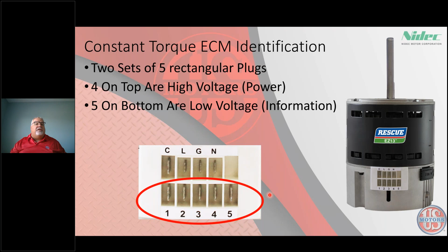So if we look at the EZ13, easy should come to mind as, okay, this motor is ready to go. It is ready to install. But remember, we have to identify, because this motor will only work with that constant torque. These low voltage pins take a 24-volt signal, and that's what tells the motor how to operate. There are 4 pins on the top, as I mentioned. Those are your high voltage. 5 on the bottom are your low voltage. So this is your identification.